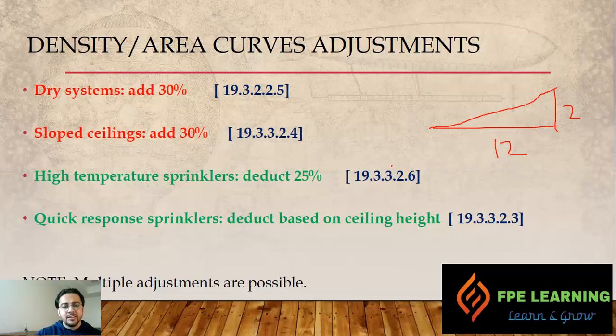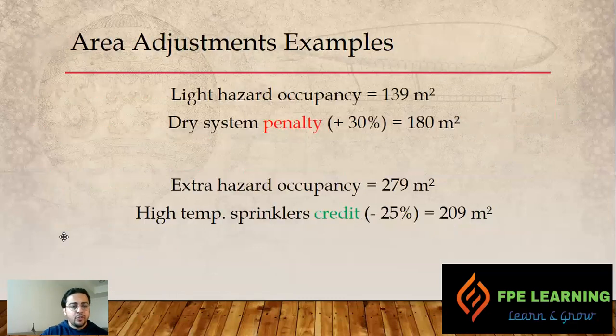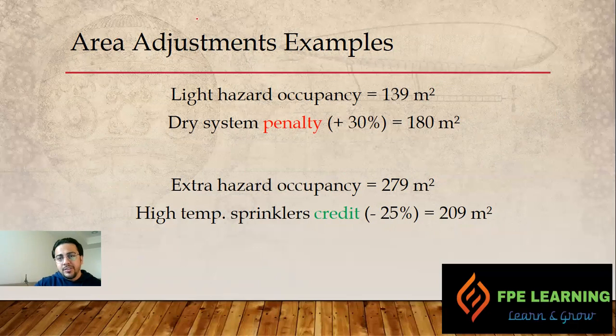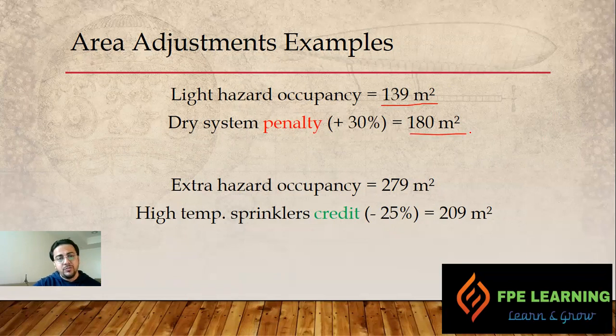Multiple adjustments can be applied together. For example, if we are designing for light hazard occupancy, the graph gives us 139 square meters. If that system is a dry system, we add 30 percent — so our design area becomes not 139 but 180 square meters. This is the area adjustment procedure in action.